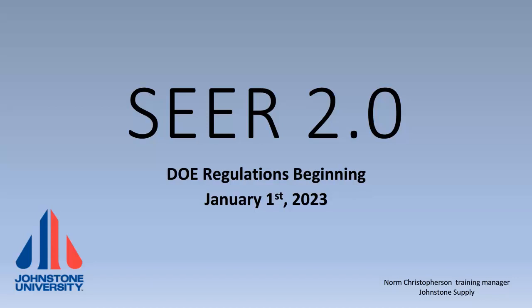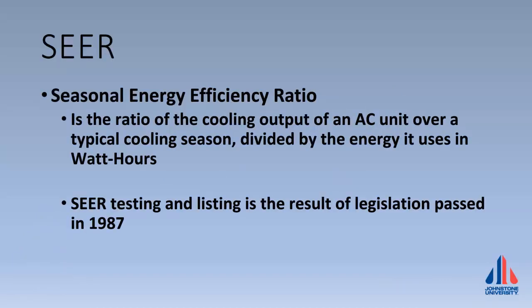So let's get going. Seasonal energy efficiency ratio is very similar to the miles per gallon rating placed on new automobiles. You know, the sticker on new cars that rate the expected fuel efficiency for that new car. The Department of Energy mandates how the rating is calculated and under what circumstances. For AC units and heat pumps, SEER is the ratio of the cooling output divided by the energy input. The higher the SEER, the more efficient the system. All of this started with regulations passed by Congress back in 1987, but now things are a bit different. Let's take a closer look.